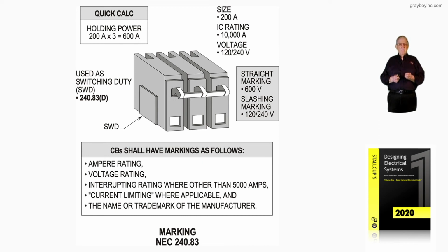Now, the name or trademark of the manufacturer would be there, such as it might be a Square D breaker, it may be a Cutler Hammer breaker, but the manufacturer is marked on there. So this illustration 9-43 simply illustrates how circuit breakers are required to be marked in accordance with NEC 240.83, so the installer will know exactly what this breaker will provide.